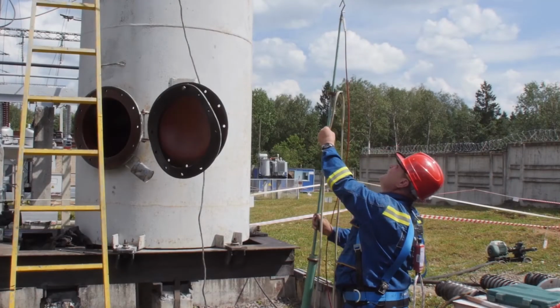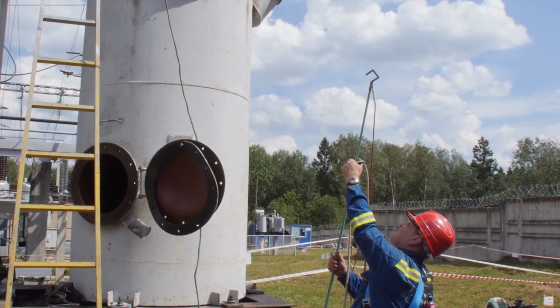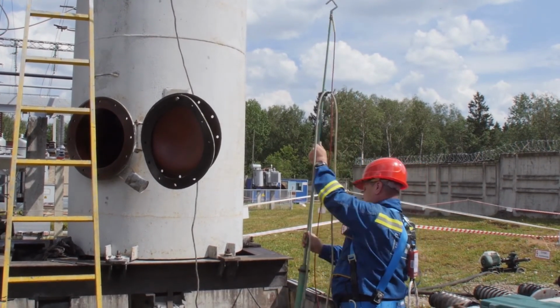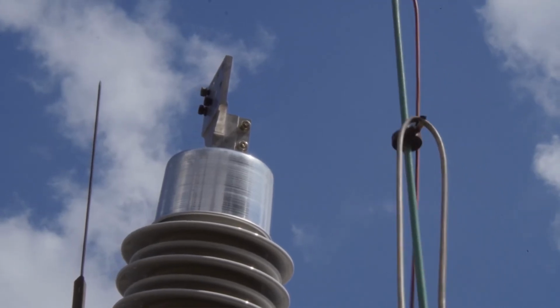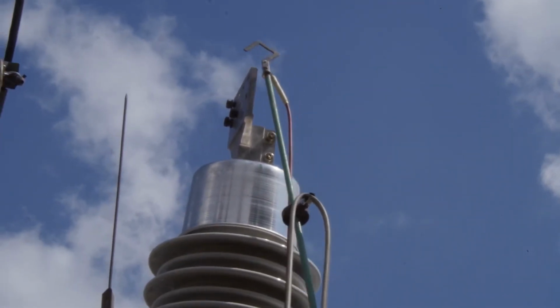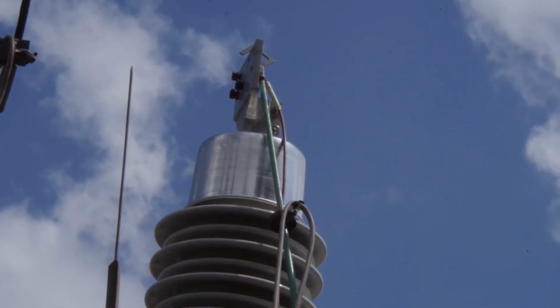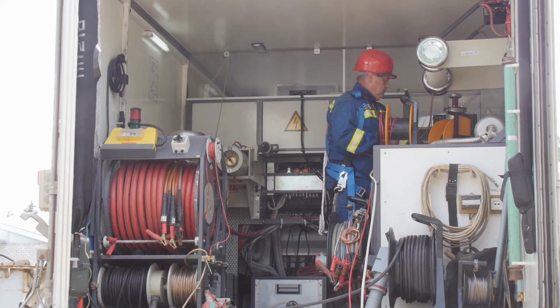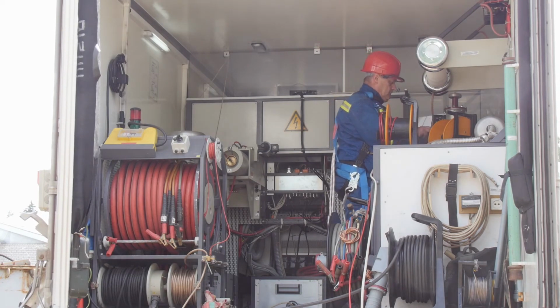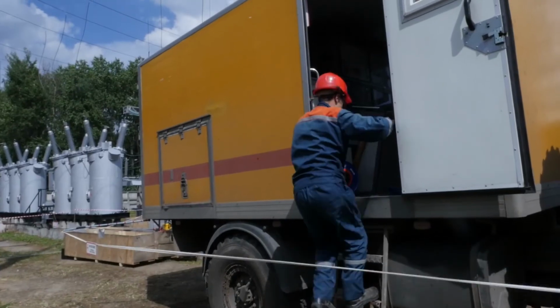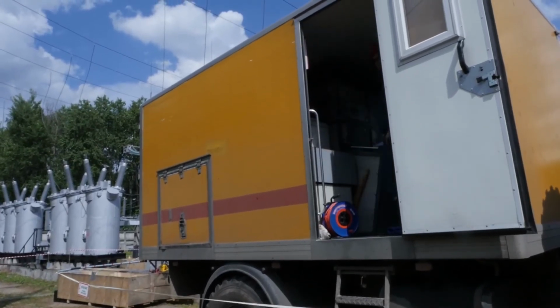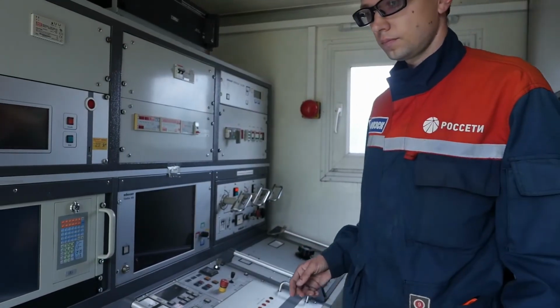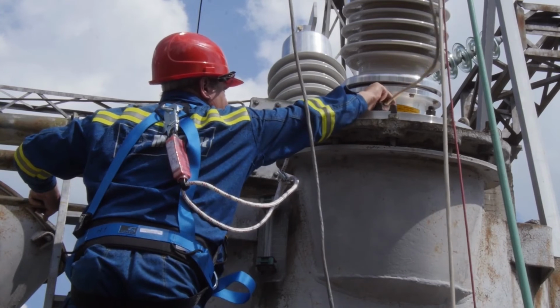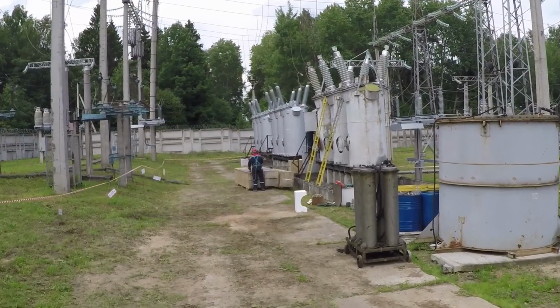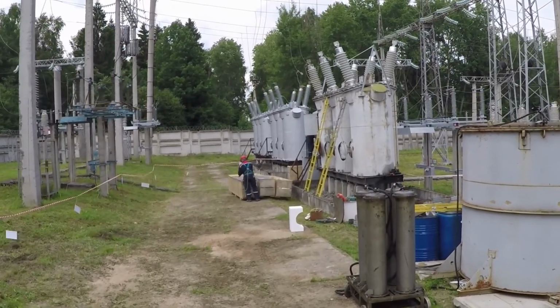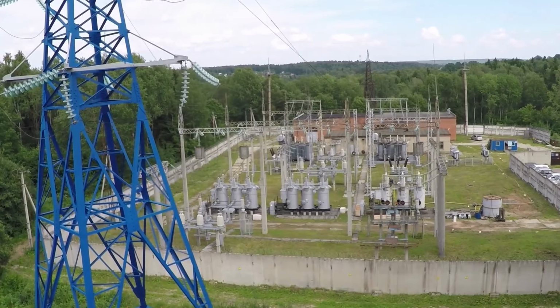Post-installation tests. After final processing, the circuit breaker is subject to electrical tests as well as testing of the bushing to a scope and using a technique specified by the bushing manufacturer. Electrical tests of the bushing after installation shall be performed by electrical laboratory experts to a scope and as per the procedure of pre-installation tests. It is to be noted that in order to avoid voltage of over 1 kilovolt at the test tap and the last bushing plate when measuring a group of bushings and applying a test voltage of 10 kilovolts to terminals of group bushings, the test tap can be ungrounded only on the bushing which is to be measured.